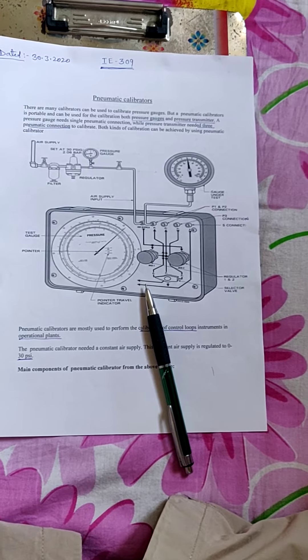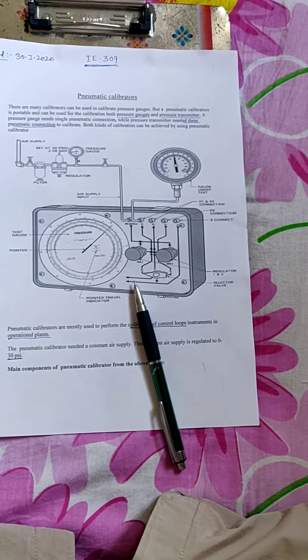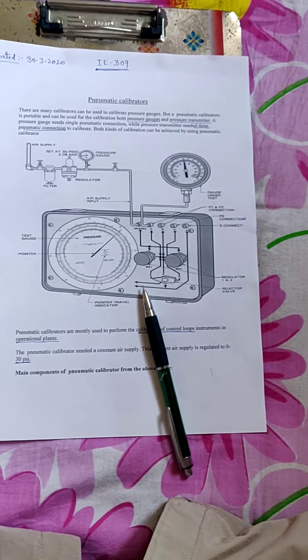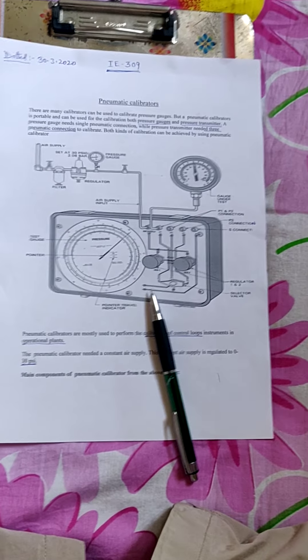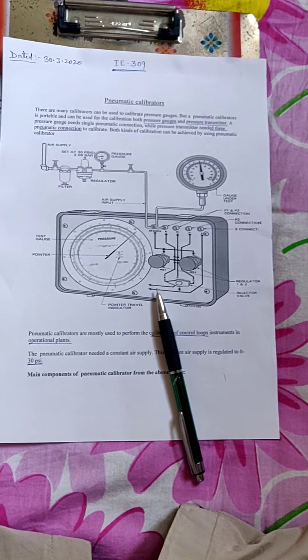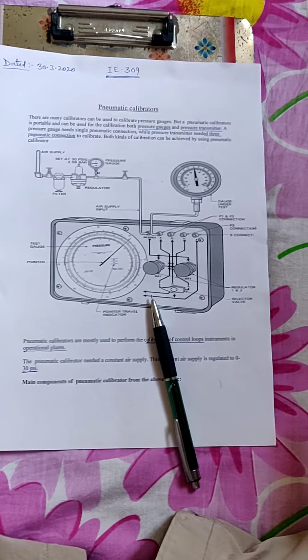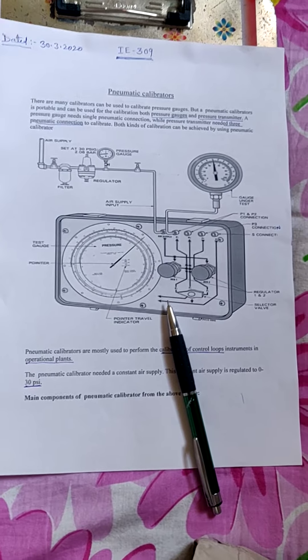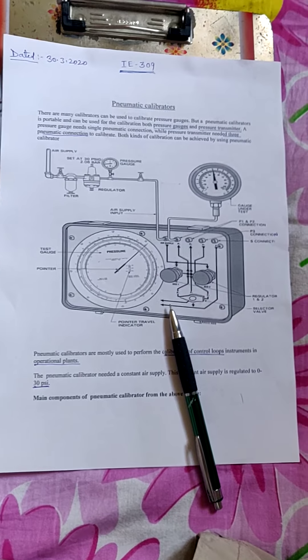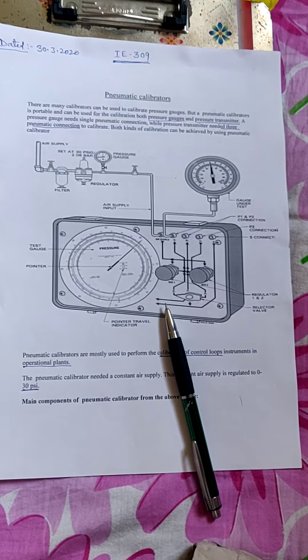As shown in the figure, here is a pressure gauge, and another pressure which is supplied by the air supply is shown here. Both pressure gauges should show the exact same value. If there is a difference, then the pressure gauge needs to be calibrated. The calibration process starts by checking the pressure from zero level up to the maximum pressure range.